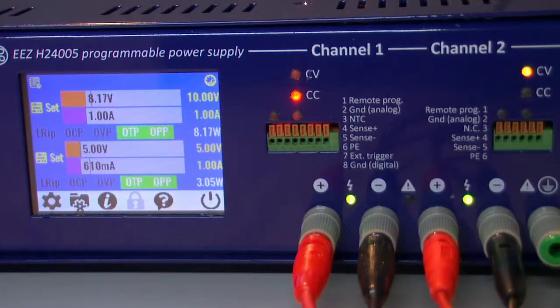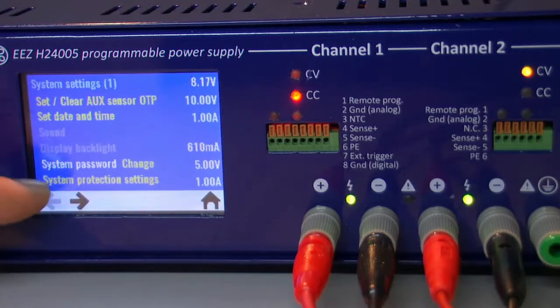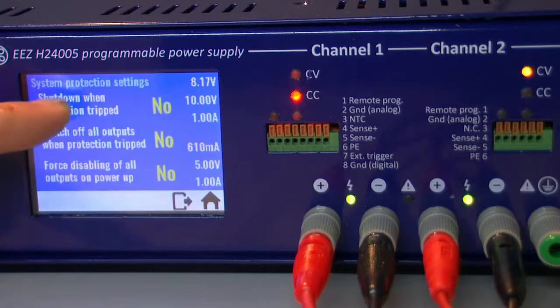And it could be interesting in the case that any of those protections tripped on one channel or both of them or whatever, the complete unit is shut down. That is possible to define by going in system settings. And under system protection settings we have shut down when protection tripped.